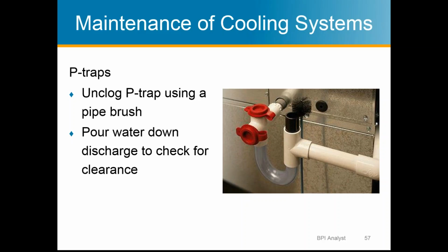So if you see water dripping from above your window, it usually means the primary system is plugged. And the main problem with plugging the primary system is what happens when the secondary system plugs: now you're going to have water overflowing. And if your system's in the attic, it's going to be overflowing onto your ceiling. So that's why you've got the two systems.